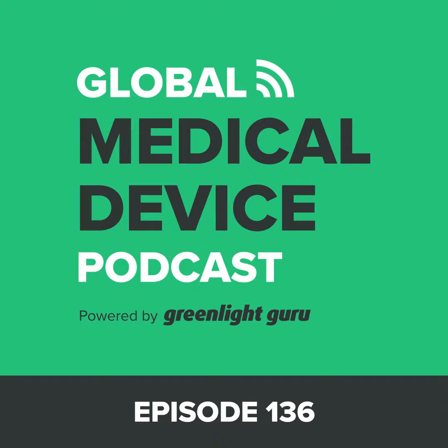So I think, in my not so humble opinion, John, it comes down to two things. First of all, what is publicly announced by FDA and the politicians is it's another way that we can try to increase the efficiency of the 510(k) review process. However, and I cannot stress this point enough, when it comes to increasing the efficiency via the eSTAR program, we are only talking about administrative review. As maybe some in our audience already know, John, when FDA reviews a submission, whether it's a 510(k) or anything else, it's a two-step process. The administrative review followed by the scientific review.